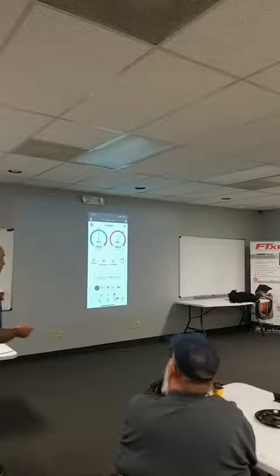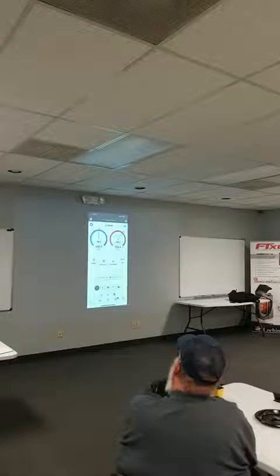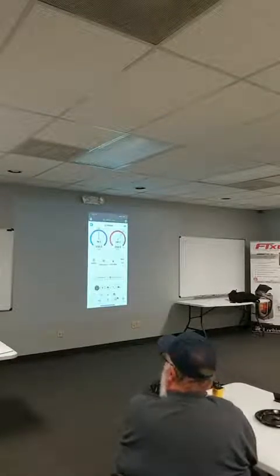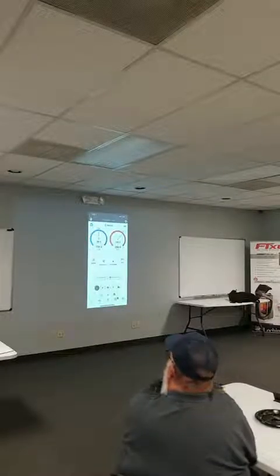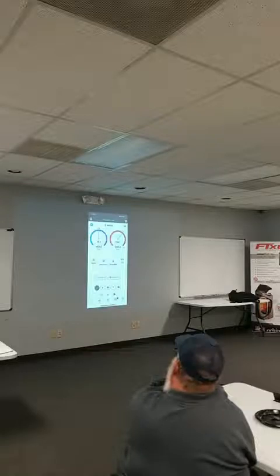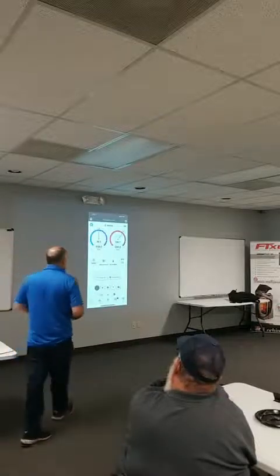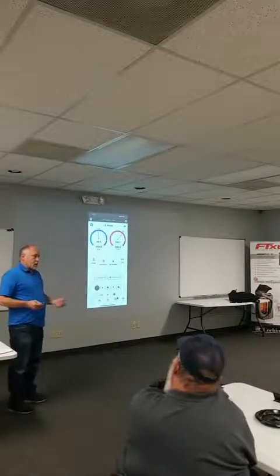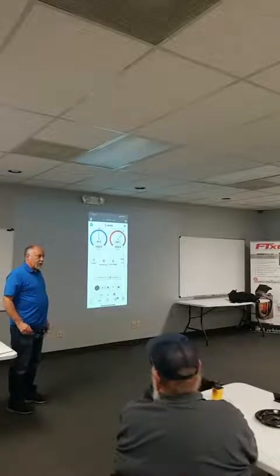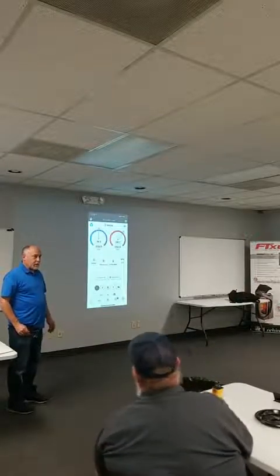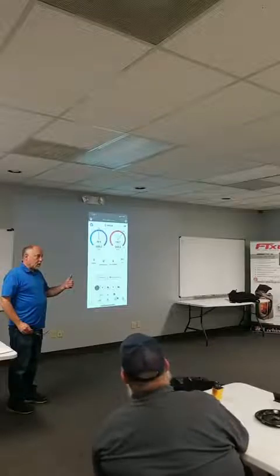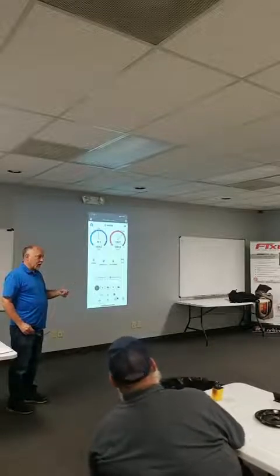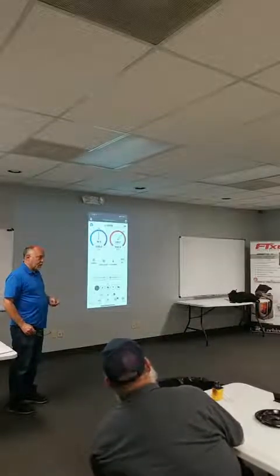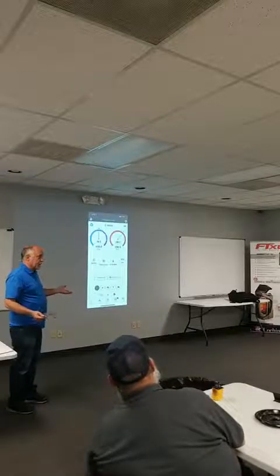Now, why would we want to shrink down the target zone on a machine? What does that do for us? When you come back to it a couple of years later, you have a reference point on where you know exactly what's changed. You know exactly how it's supposed to run. And what do you think it does for diagnostics? Here's the question. If I told you the system had an undercharged fixed orifice system, you'd expect to see low suction pressure, high superheat, low subcooling, low head pressure, right? Undercharge of a system, classic conditions.